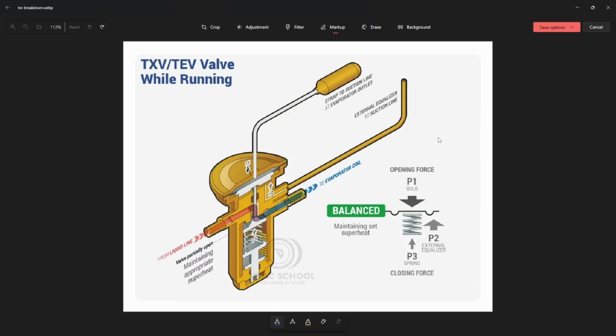So when it comes to selecting a TXV or an EEV, you'll find most often that EEVs are found on high efficiency units, especially on inverter driven systems, because inverter driven compressors need a valve that can keep up with their modulation. They don't have time to wait for a TXV to catch up to the compressor's change in speeds. If we wait on a TXV to try and catch up to our compressor as it modulates, most of the time you'll find that the TXV can't keep up and we end up with 0 degrees or less of superheat. And then we end up with liquid refrigerant getting back to our compressor, slugging our compressor with liquid, damaging our compressor, and leading to compressor failure. So that's the main reason why we have EEVs over TXVs. They're just faster and it's better application on inverter driven systems.